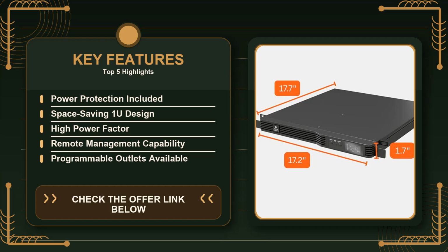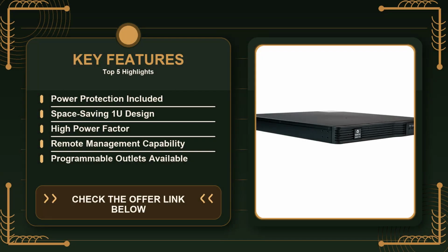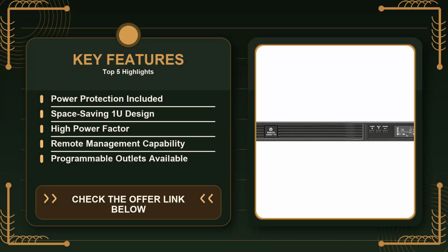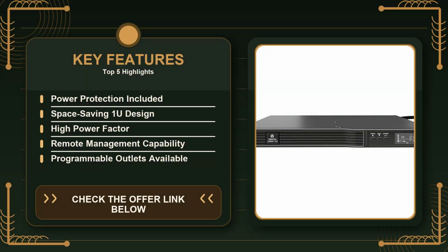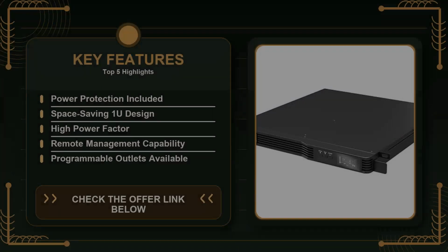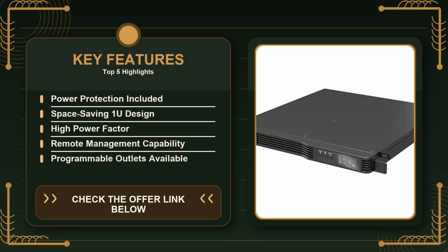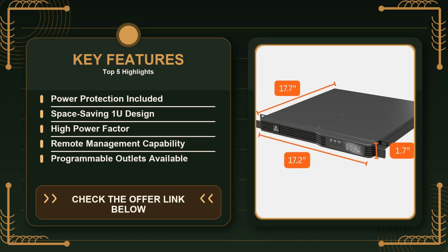Another point where the PSI5 stands out is its high power factor of 0.9. In many data center environments, a low power factor can cause your utility bill to balloon because utilities charge for reactive power. A 0.9 factor keeps the apparent power close to the real power you're actually using, meaning you're not paying extra just because of inefficiencies. In practice, that translates to a modest reduction in operating costs over time, especially if you're running the UPS at near full load on a regular basis.